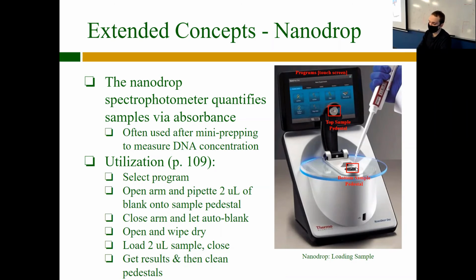Load those 2 microliters onto a little pedestal here. It's very, very tiny. You have to put the end of your pipette right in the center of the pedestal. It's not too difficult. It's easier than it looks because the surface tension of this droplet of water is so high. It typically fits right on the pedestal, no problem at all. Though if you mess up, just pull out some wipes, wipe off the pedestal. If you closed it and messed up, wipe off that pedestal too, and then reload your samples.